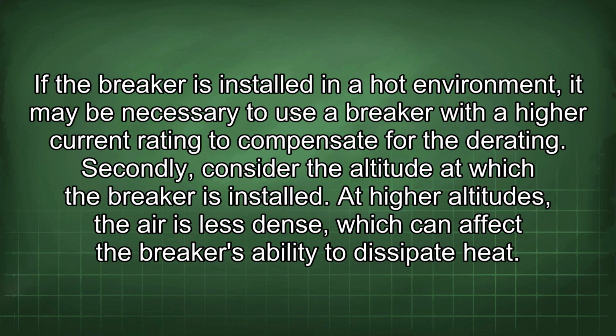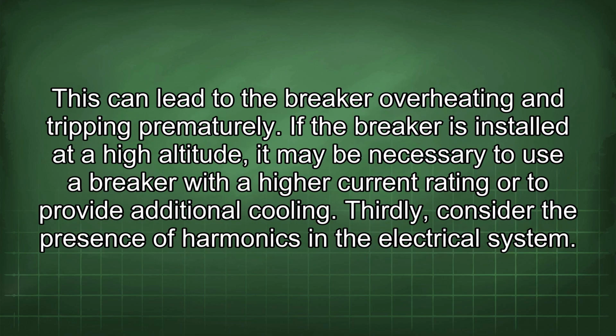Secondly, consider the altitude at which the breaker is installed. At higher altitudes, the air is less dense, which can affect the breaker's ability to dissipate heat. This can lead to the breaker overheating and tripping prematurely. If the breaker is installed at a high altitude, it may be necessary to use a breaker with a higher current rating or to provide additional cooling.